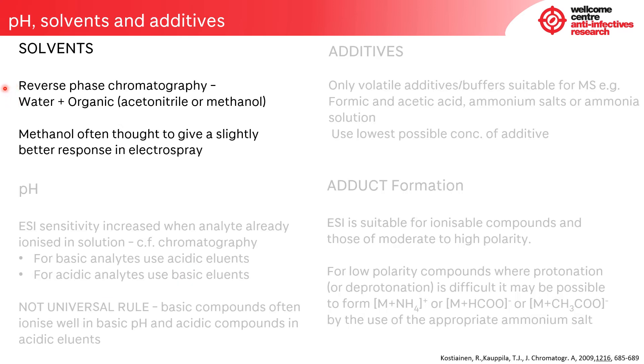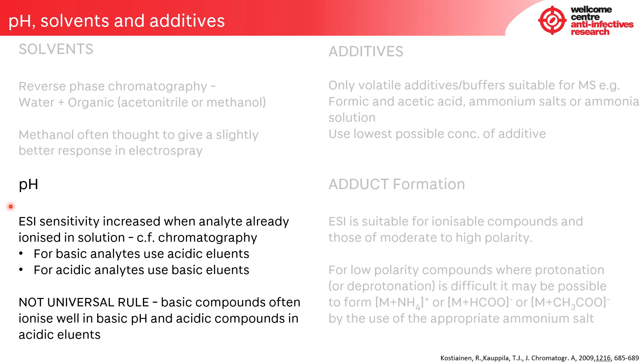In DMPK and medicinal chemistry, the majority of analysis is done using reverse phase chromatography, using water and either acetonitrile or methanol as the organic eluent. In mass spec terms, there's relatively little difference between using acetonitrile or methanol, although a number of people think that methanol gives a slightly higher response in electrospray. Looking at the effect of pH on electrospray response, sensitivity usually increases when an analyte is already ionized in solution. So as a rule of thumb, basic analytes use acidic eluents and acidic analytes use basic eluents, though this is not a universal rule and compounds often ionize well outside these guidelines.